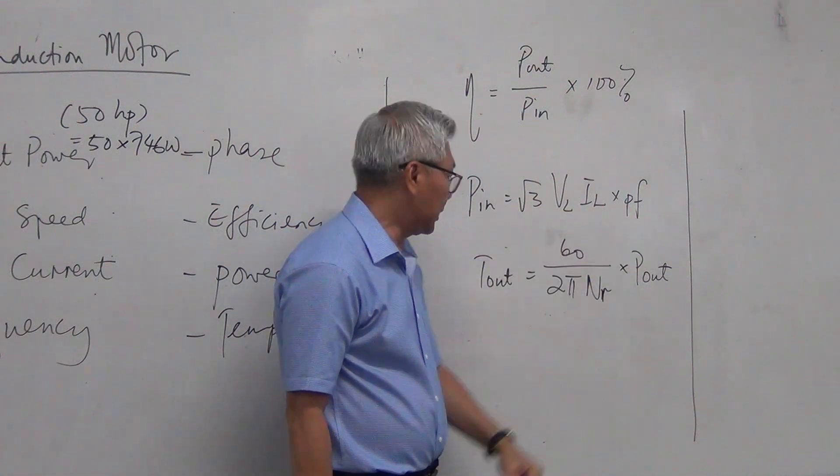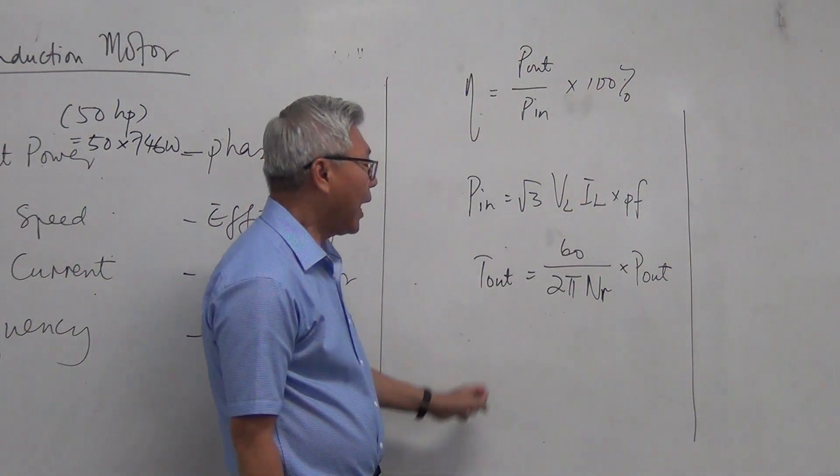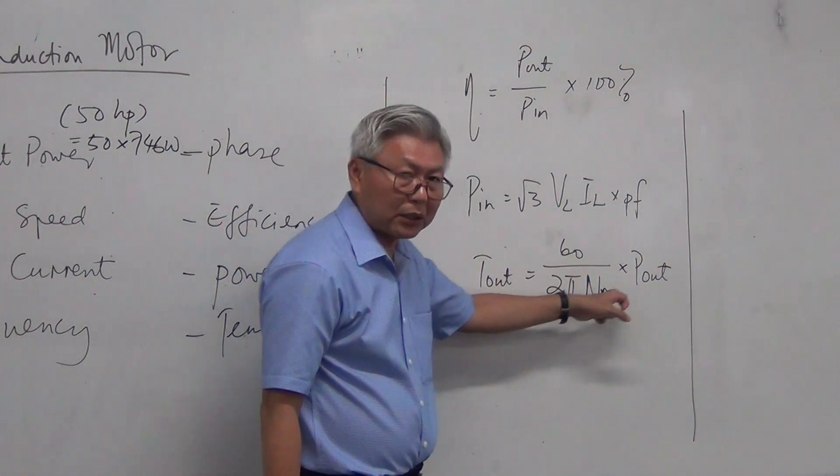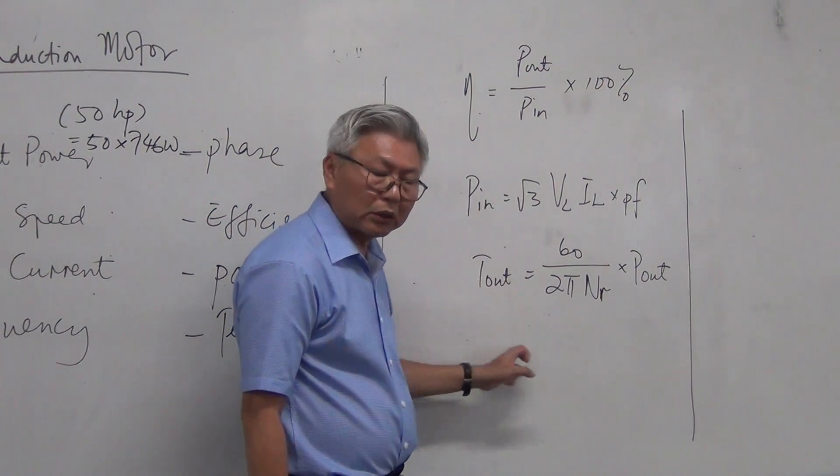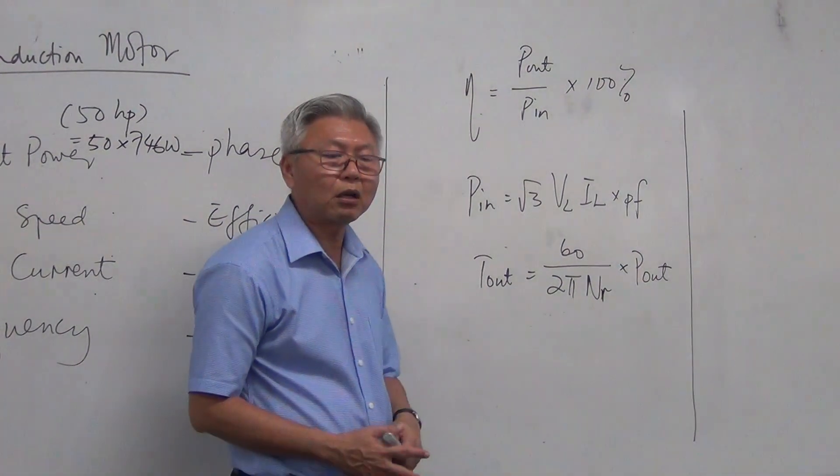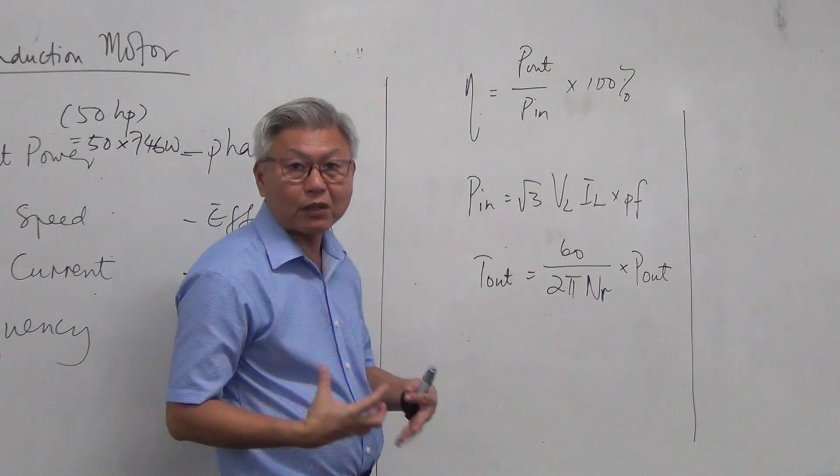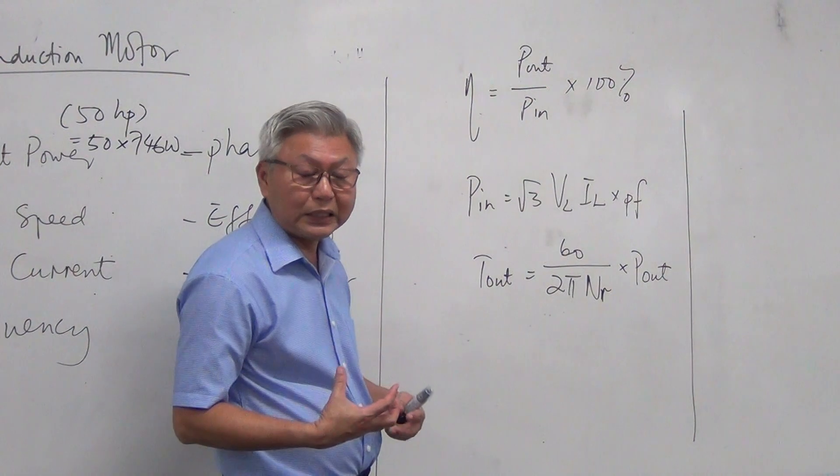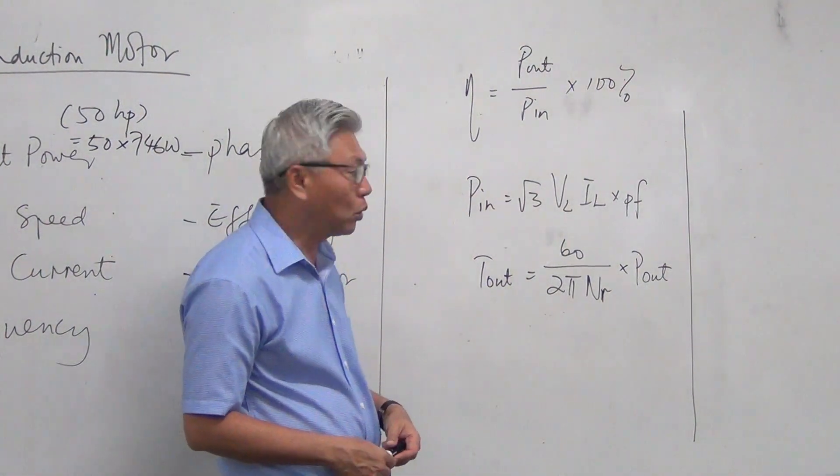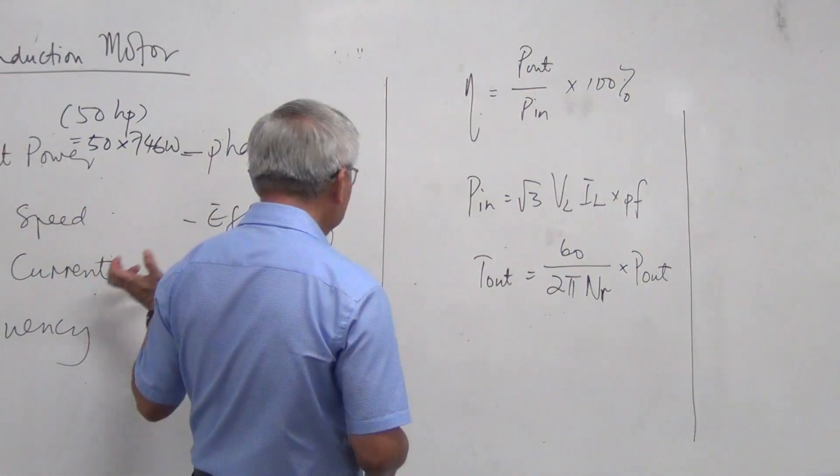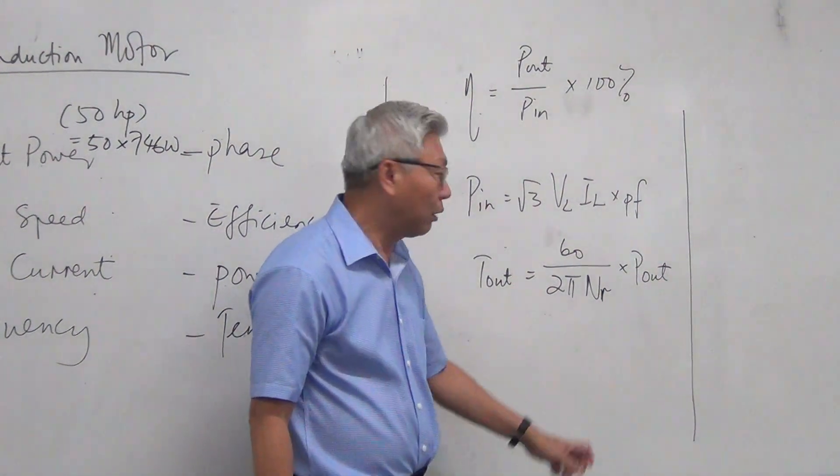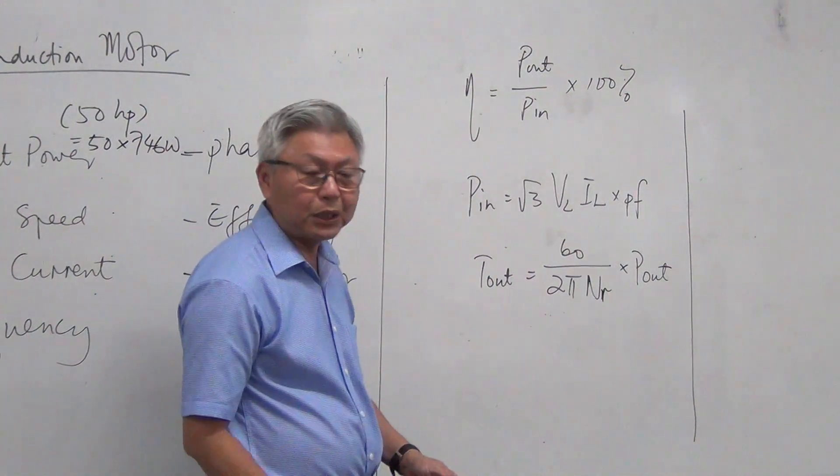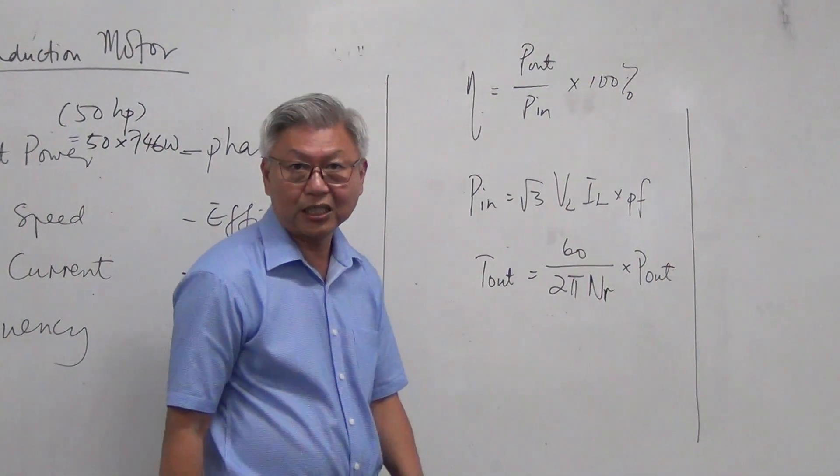And the torque formula is still the same as our DC motor. 60 over 2 pi n multiplied by output power. Now, we need to know how to calculate torque, because a lot of time when you use a motor, it's because you want to use it for certain application. So you need to size up the motor according to the work needed or the torque needed. So with the power that's given, you are able to calculate out the torque value with the speed, with the speed that you want to operate the motor at. At the particular speed, what is the torque it can take?